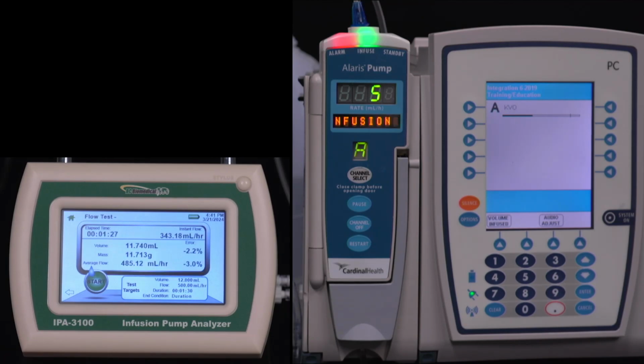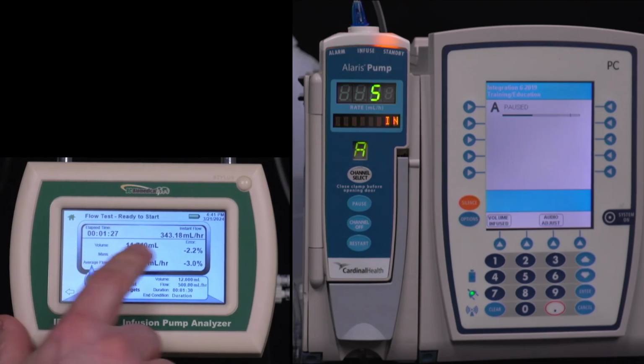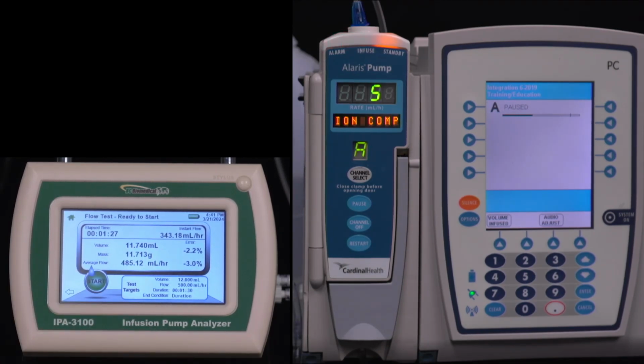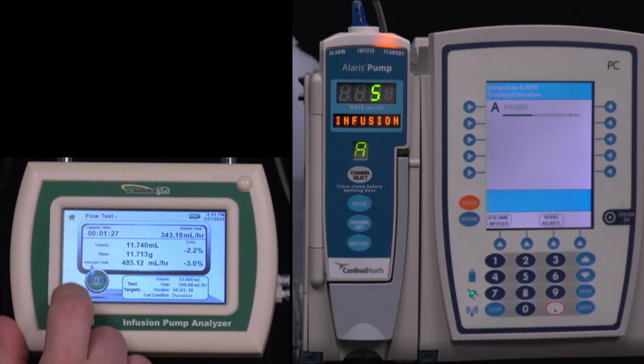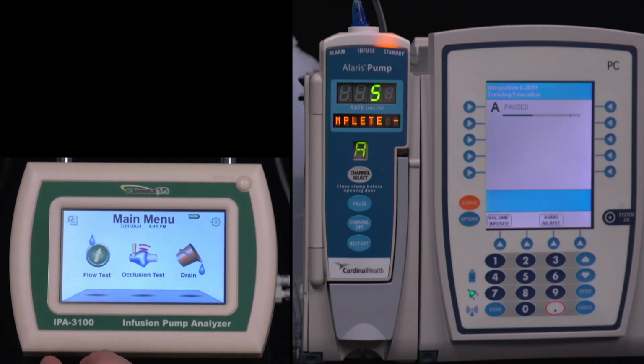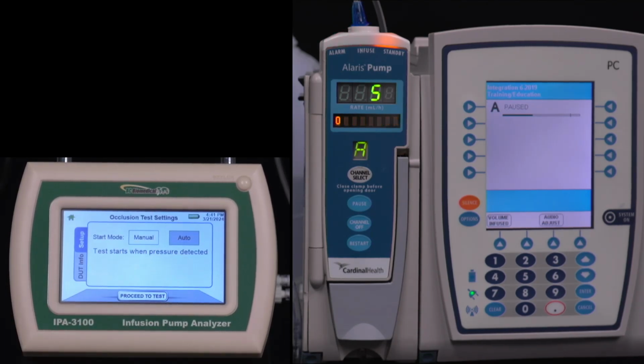Okay, so there's my test results there. I'm going to go ahead and pause the pump. I've got my readings for volume. We dispensed 11.7, and that grams is 11.713. So here we've got our test results. We can record those as needed and compare them against the settings in the service manual and determine whether it's good or bad.